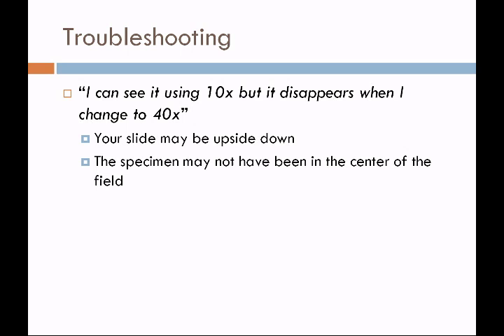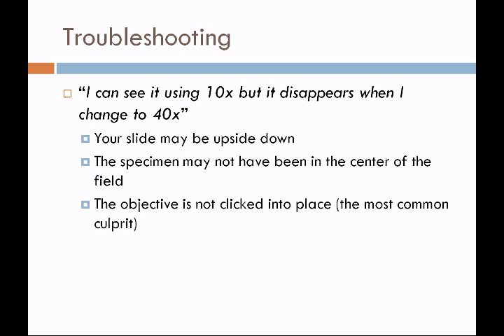Another issue is you might not have put your specimen in the center of the field. If it's in the center, when you switch your objective lens it will still be in the center. However, because the area of the slide you are looking at becomes smaller as you increase magnification, if your specimen is at 1 o'clock or 2 o'clock, you might not see it after switching. Also, if you don't click the objective into place, you're not going to have a straight path of light and you're not going to see anything. This is probably the most common error — just check that your objective is clicked into place. You will hear the click when it's in the proper seating.